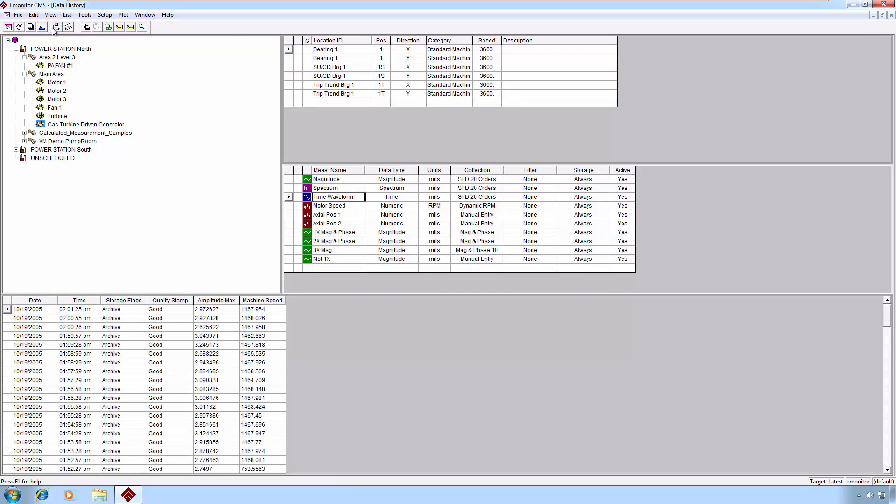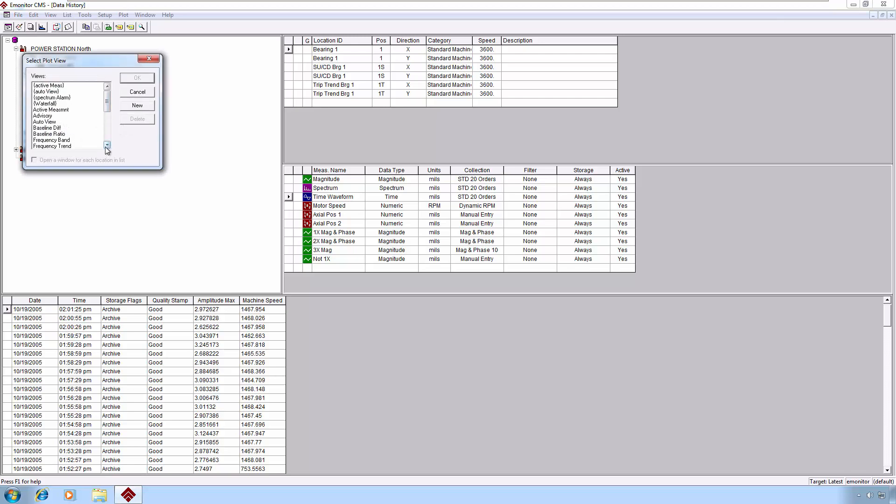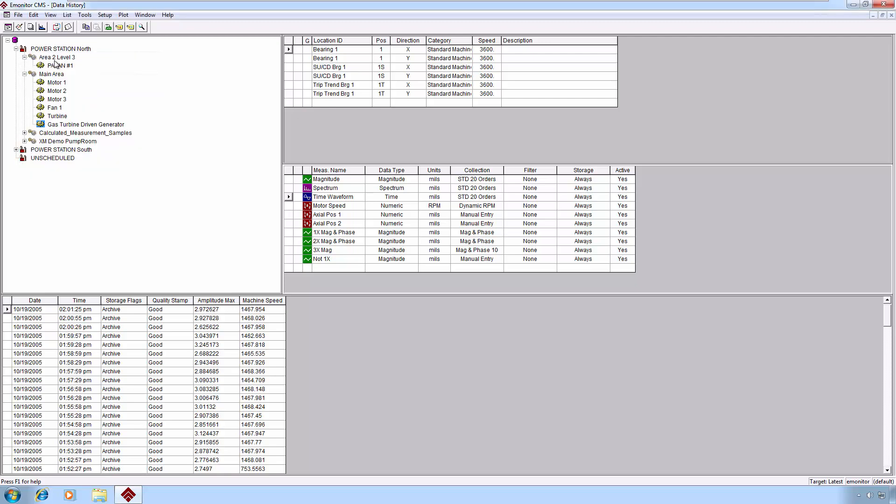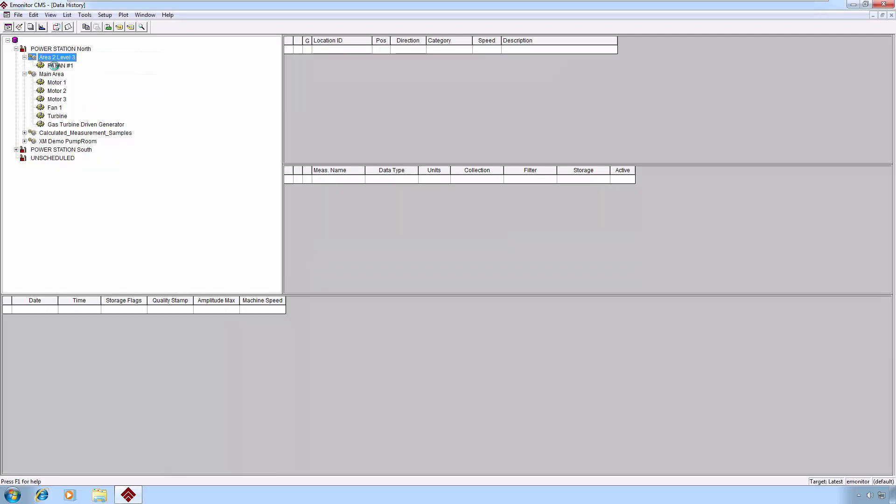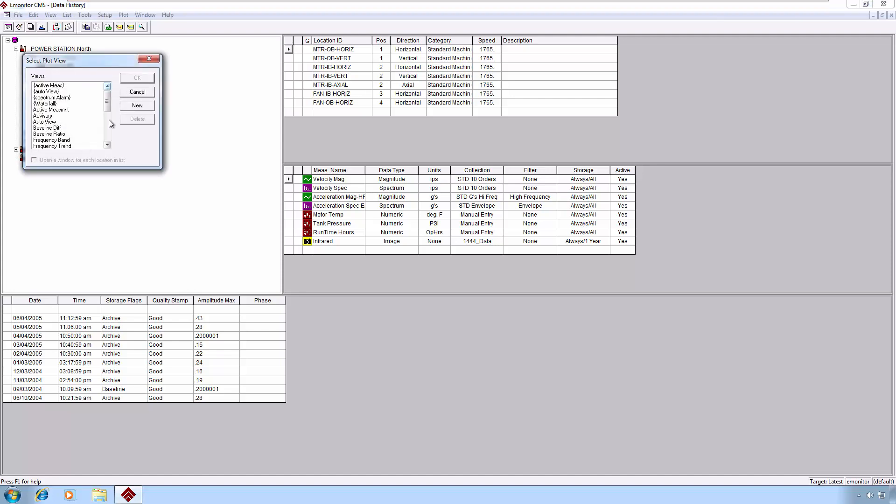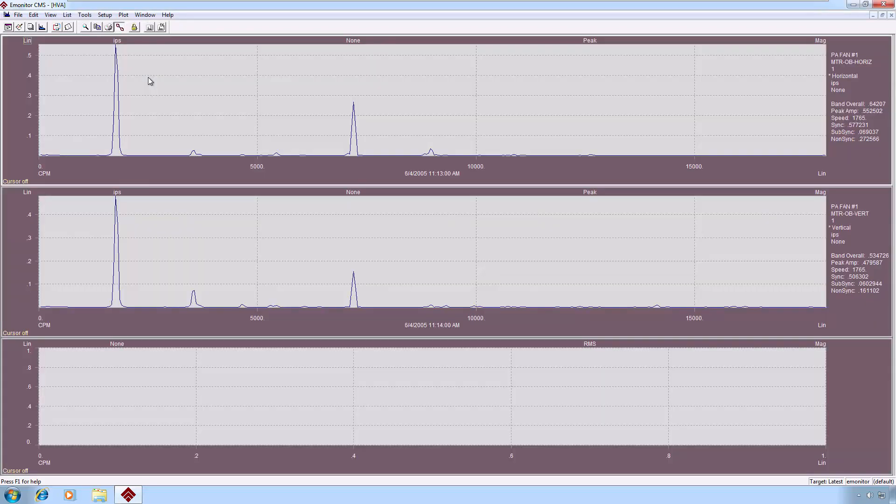Let's continue on with some other options here. The HVA plot gives us horizontal, vertical, and axial spectra if we're taking all those directions. So let me again switch data and go back to my regular PA fan here. Come back and pick my horizontal, vertical, and axial, and we will get three plot panes. In this case, I'm not taking an axial spectrum, but I am taking the horizontal and vertical.